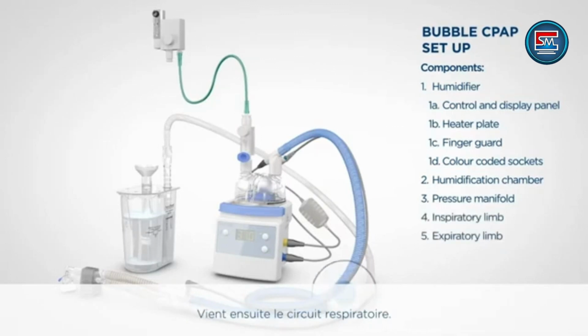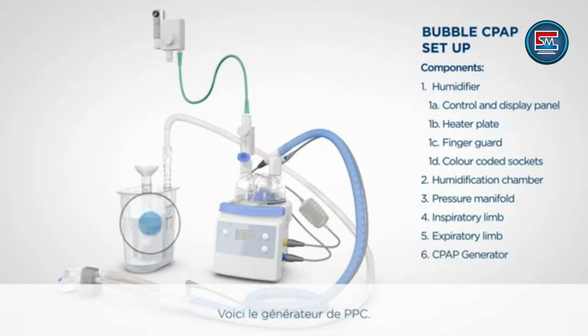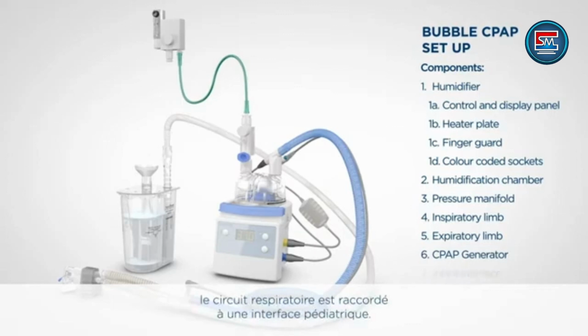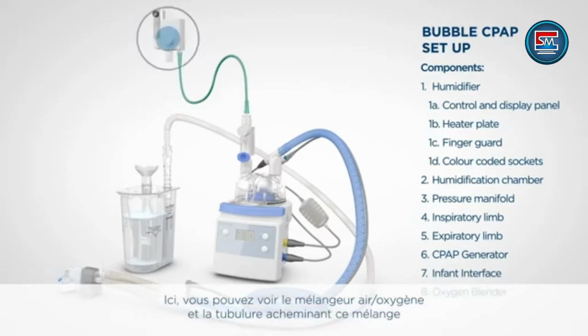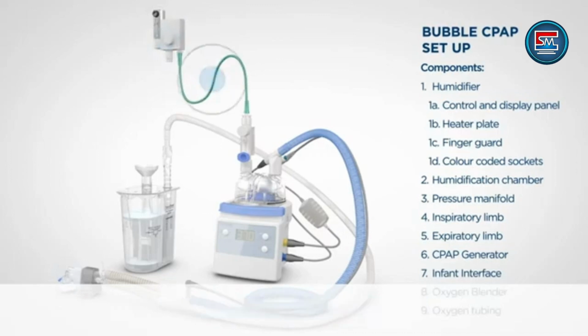This is the breathing circuit. It carries humidified gas to the patient. It also carries the expired gas back to the CPAP generator. This is the CPAP generator. It maintains mean CPAP pressure. In this setup, you can see the breathing circuit attached to an infant interface. You can also see the oxygen blender and oxygen tubing used to complete the Bubble CPAP delivery system.